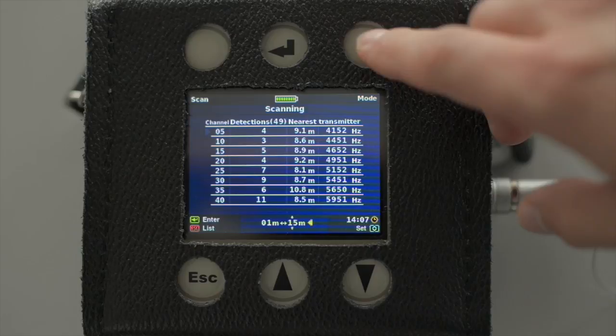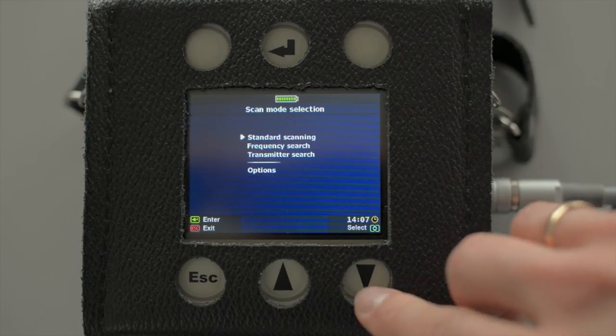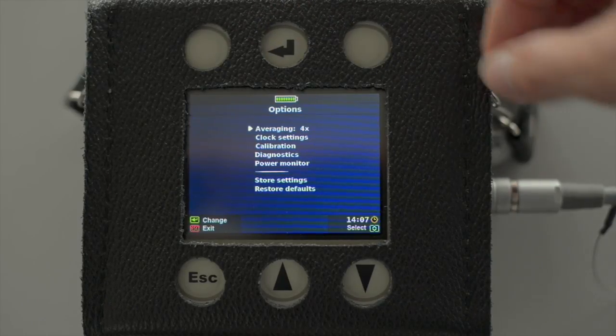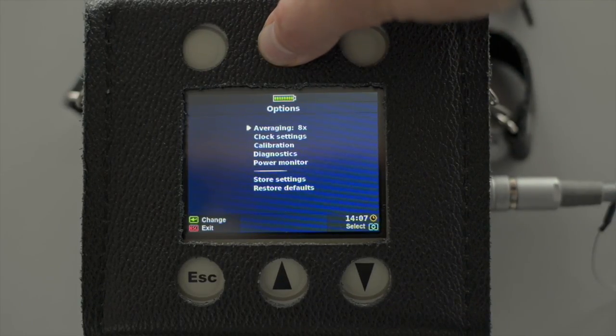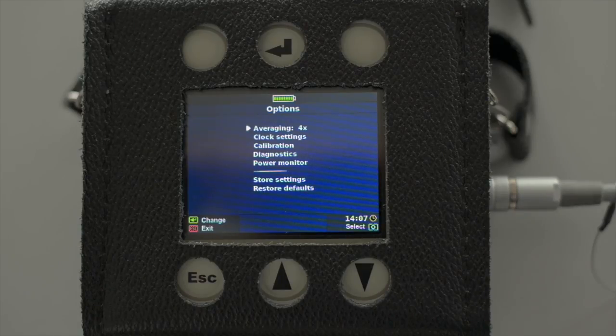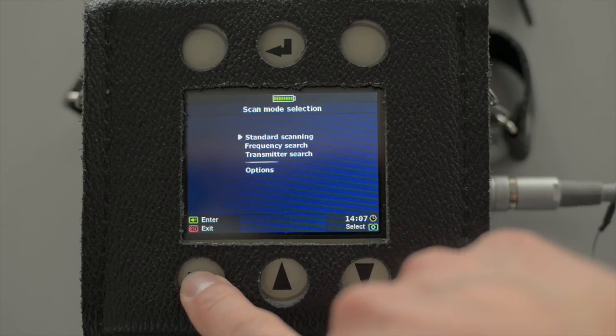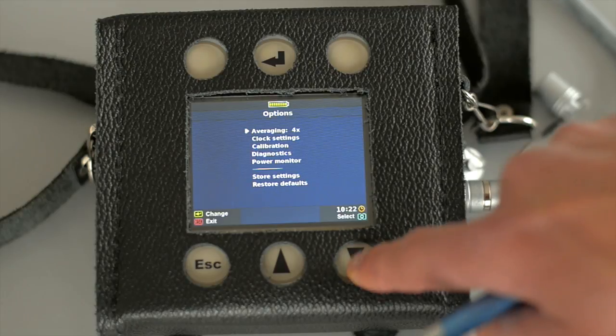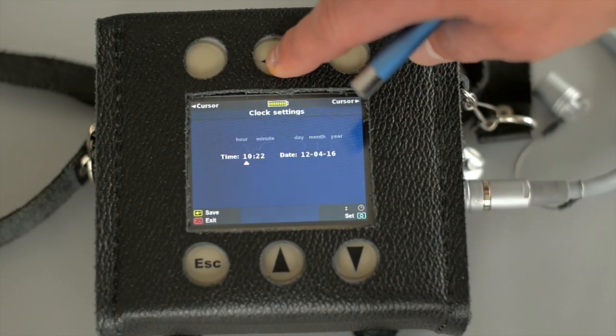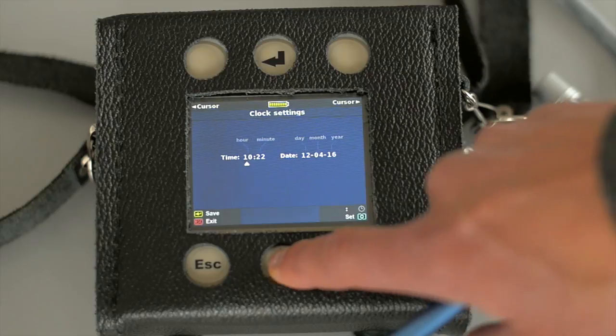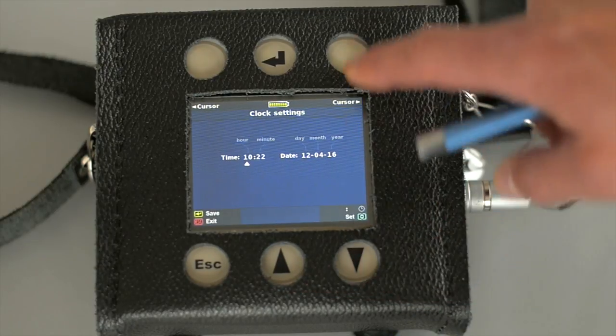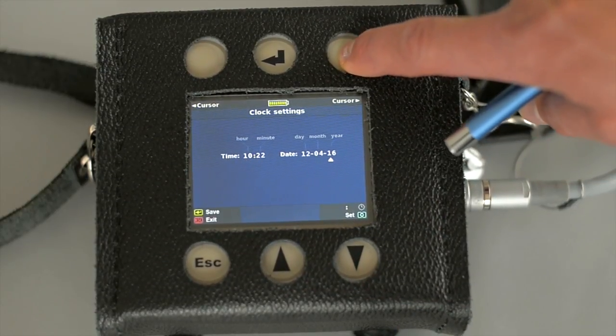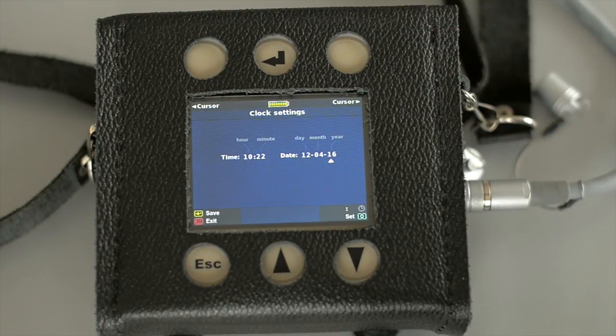Now we'll show you how to set the averaging function in the Options menu. It is used to set the number of measurements during scanning before the result is displayed. The higher number we choose here, the better result we'll get, but the duration of the measurement will be proportionally longer. Now we'll show you how to set the clock. While in the Options menu, we choose Clock Settings. We choose digits with the cursor left and cursor right keys and set the digits with the up and down keys.